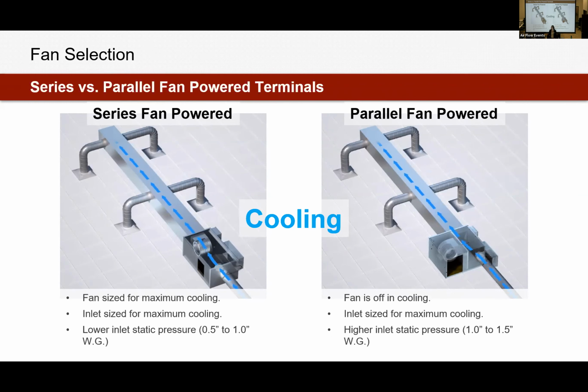How do they operate differently? In cooling, for a series box, because our fan is on the discharge, our fan always has to be running to provide any air to the space. So in cooling, our fresh air through the valve, our cooling airflow, will match the fan flow. We're just gonna send everything downstream. Essentially, this is acting like a booster box. Say we've got 1,000 CFM through the valve, our fan is running at 1,000 CFM. We're just gonna continue to move that downstream.